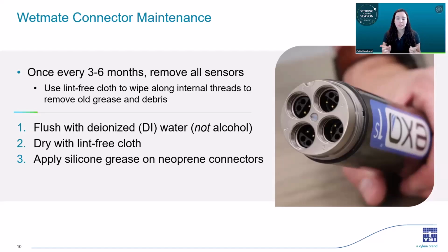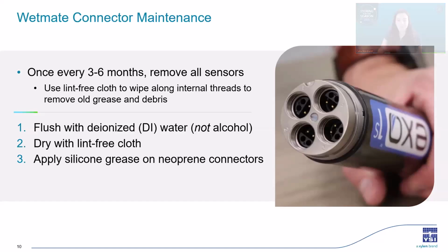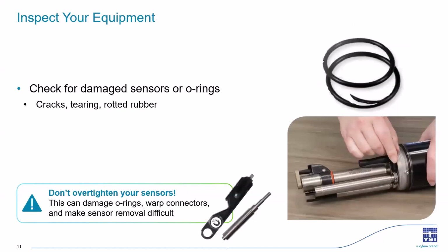But make sure you re-grease the neoprene rubber on the connectors and the bulkhead ports. You're just going to use a small amount of silicone grease on your finger and rub it in there. Or use a flux brush to help you coat the black rubber. And we just need enough to make the surface shiny. So while you're cleaning your equipment, take the opportunity to inspect everything for damage, including the instrument itself, the sensors, and the O-rings. Look for cracks in the plastic or maybe tearing or old rotted rubber.